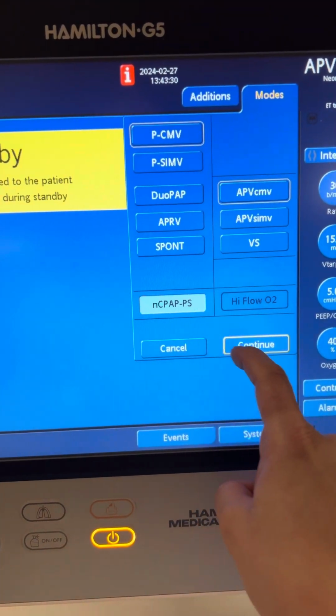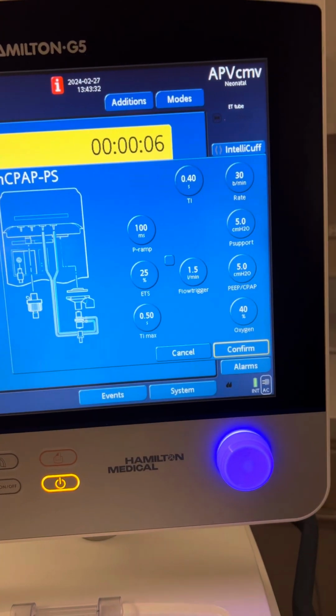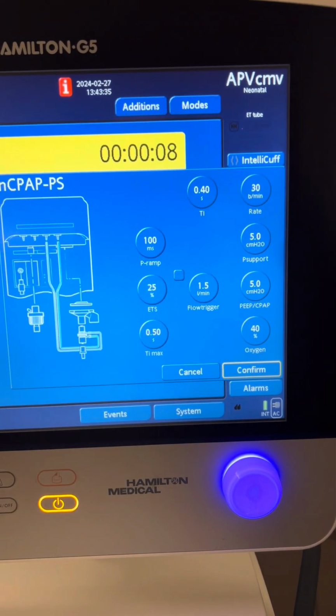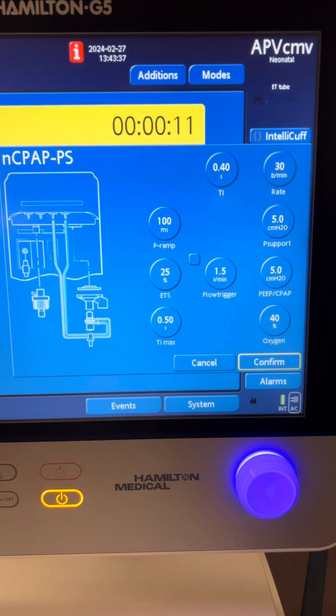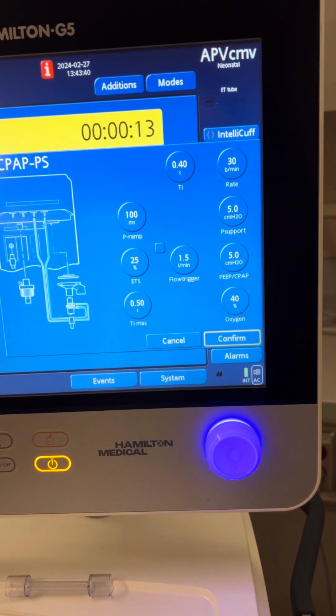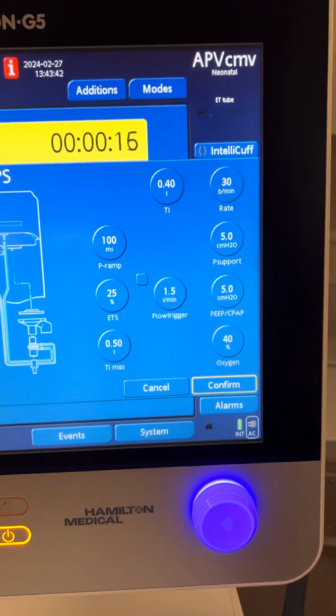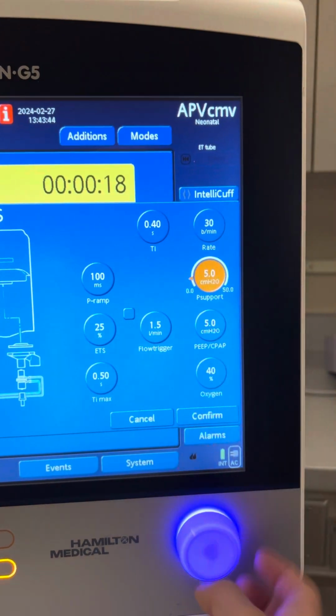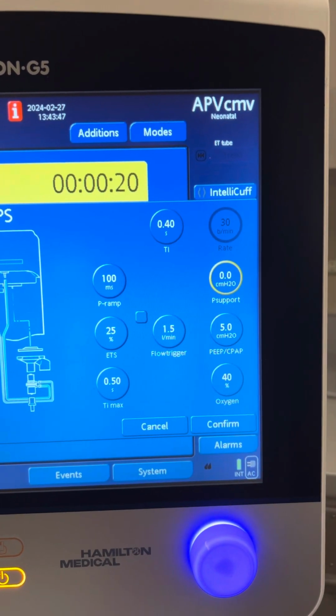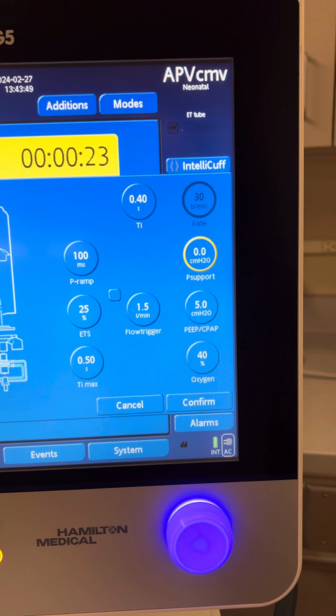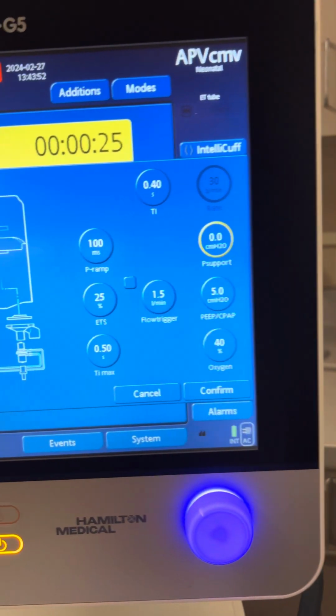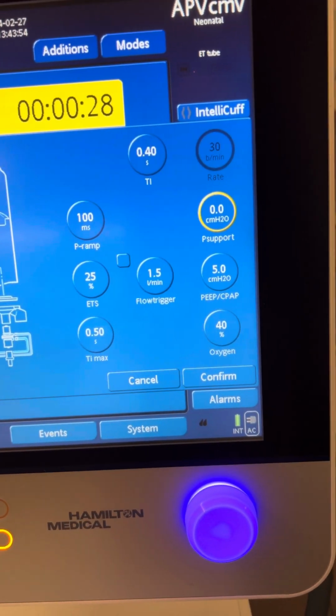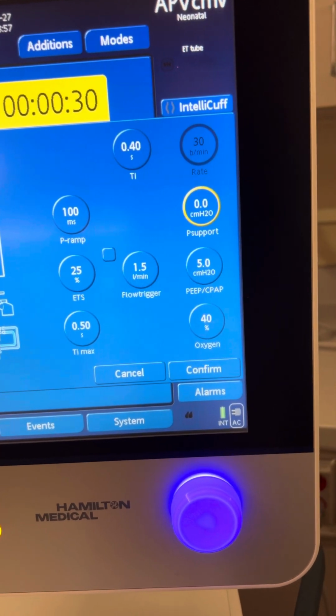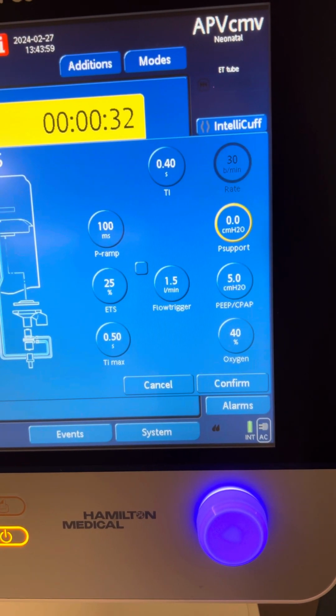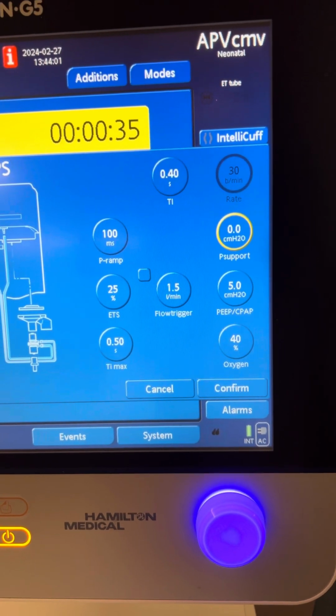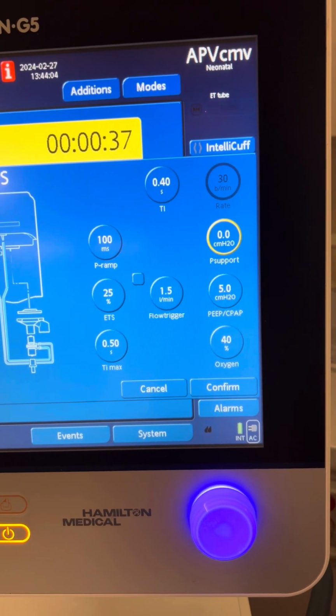And then if you're going to do nasal CPAP, you can do RAM cannula on this setup, and you can also do the trunk that we do for bubble CPAP if we need to get a better seal and deliver that pressure more effectively. If you turn the pressure support off, they'll no longer get that backup rate. It'll go to gray there, and this would be just like doing 5 of CPAP. In terms of the flow trigger, you may have to start a little lower. It will default here just based on recommended settings from Hamilton, but you may need to go down on it in case your patient has some missed triggers.